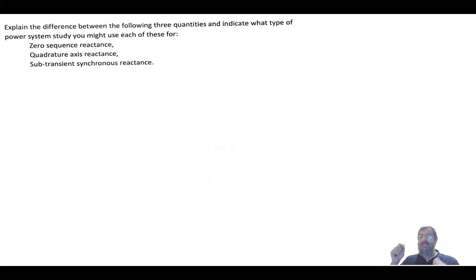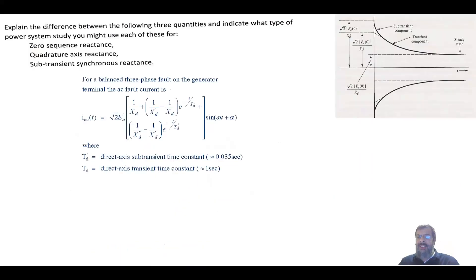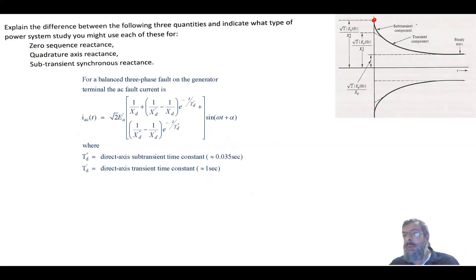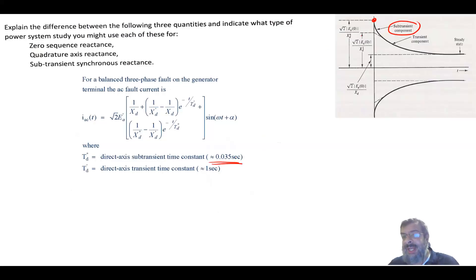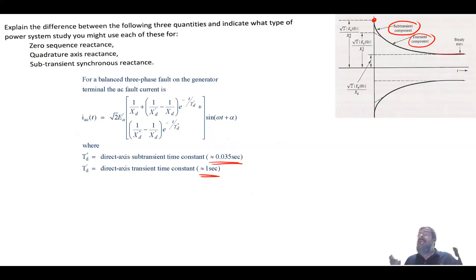The last quantity is the sub-transient synchronous reactance. When a generator is subjected to a fault — symmetrical or unsymmetrical — the fault current starts very high and gradually reduces. It begins with the sub-transient component, which lasts a very short period, around 35 to 50 milliseconds or a few cycles. After that, the current drops to the transient component, which lasts about one second, and then the current reaches steady state until the fault is cleared.